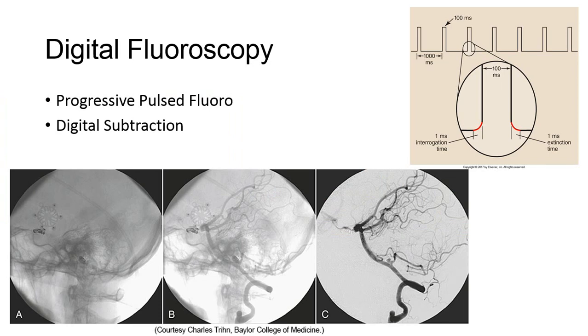With digital fluoroscopy, the individual image frames allow image subtraction techniques to be used, which can be extremely advantageous for exams using intravenous contrast media injection. The exposure time for each pulse, called the pulse width, can be adjusted from 3 to 10 milliseconds. Combining this feature with a standard mA setting, the dose can be significantly reduced.